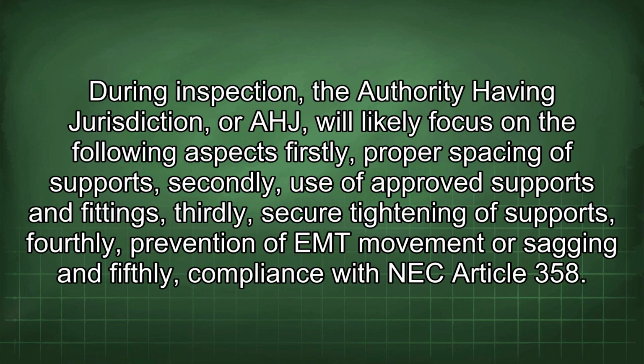During inspection, the authority having jurisdiction, or AHJ, will likely focus on the following aspects: firstly, proper spacing of supports; secondly, use of approved supports and fittings; thirdly, secure tightening of supports; fourthly, prevention of EMT movement or sagging; and fifthly, compliance with NEC Article 358.